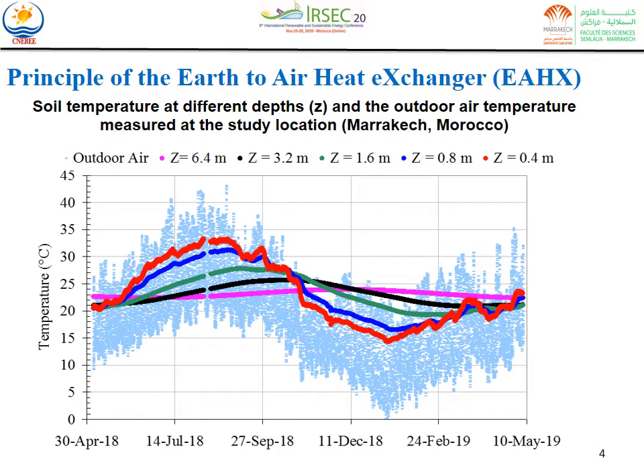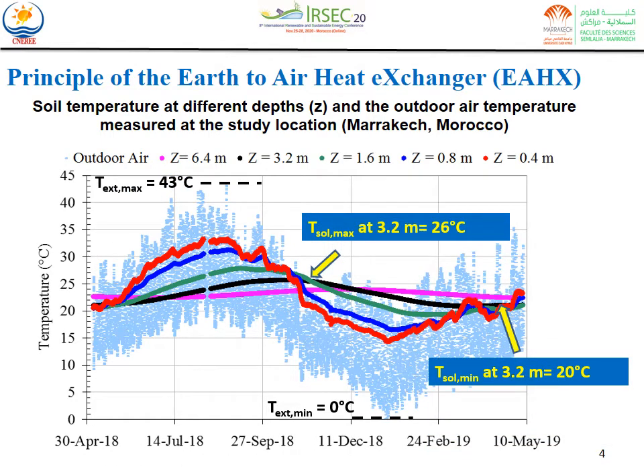This system uses the underground as a heat source or sink to heat or to cool the outdoor air. Thanks to the thermal inertia of the soil, the underground temperature is lower than the outdoor one in summer and higher in the winter. So the principle is very simple. Outside air is blown through buried pipes and gets heated or cooled and then used to produce indoor thermal comfort conditions in the building. So we can use it for cooling as well as for heating. But in this work, we are interested in the cooling purpose.